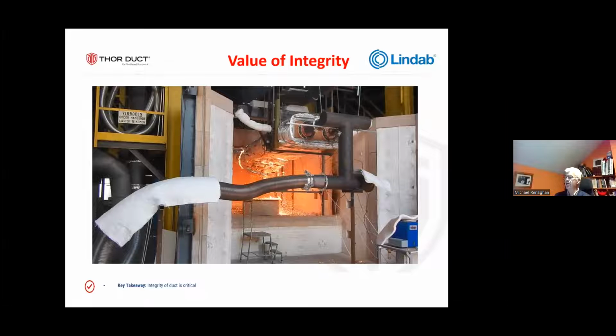Okay, so we have a scenario here where we have a duct that's in a fire. You can see it's glowing orange here, and the fans are connected here to exhaust the air. So the smoke's been exhausted. But you can see the line of the duct. There's the bracket. And what's happened is the duct has become like a snake because of the amount of heat that's going through the duct.